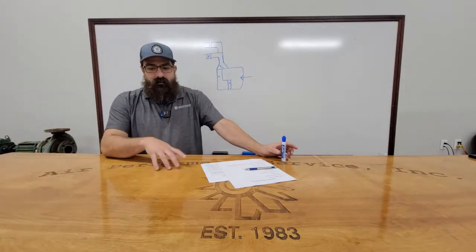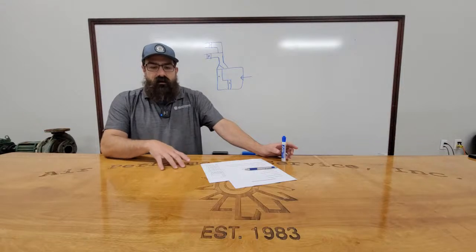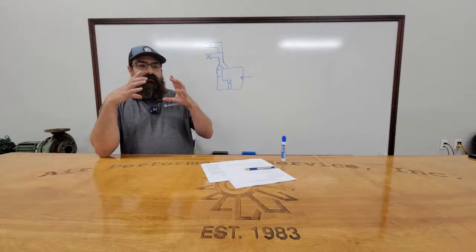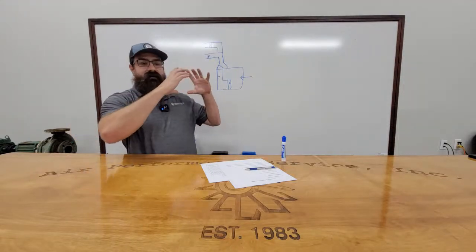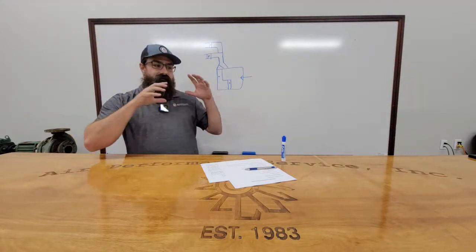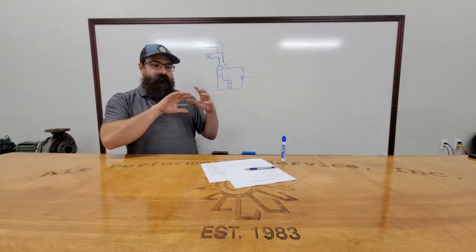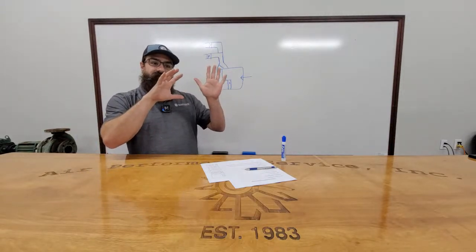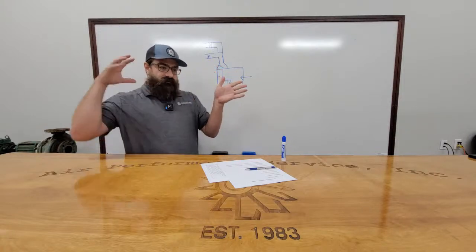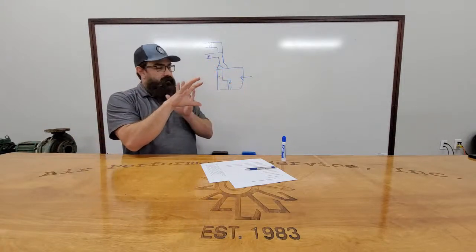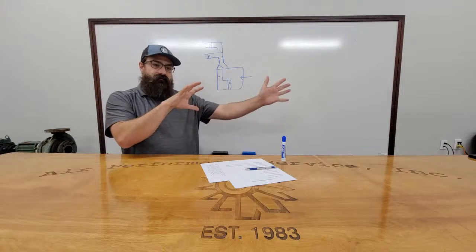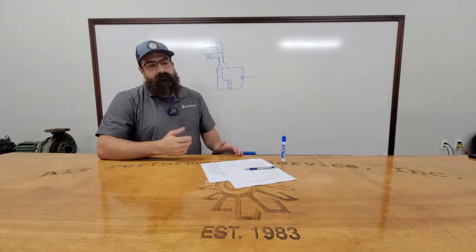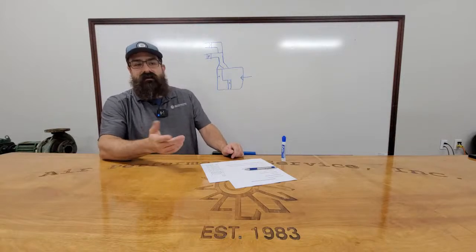Like, we did a retrofit a couple years ago on a building that had a ton of split systems. Every split system had like a 6-inch duct that was literally right next to the return of it. And then some of them, even the newer ones, when we would replace them, they would actually duct it into the unit after the return filter. So it would just come into a little plenum. You'd have your face right here with your filters, and then this little 6-inch duct would just come into the return plenum. Same type of thing you're talking about in theory.